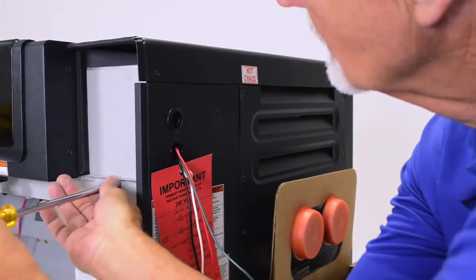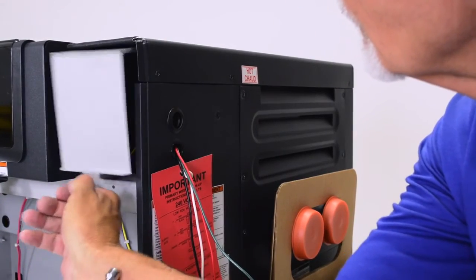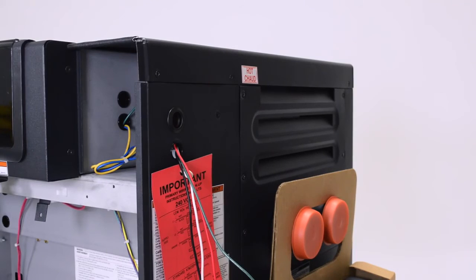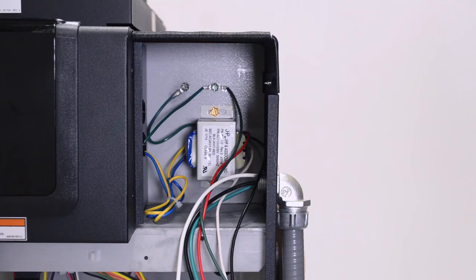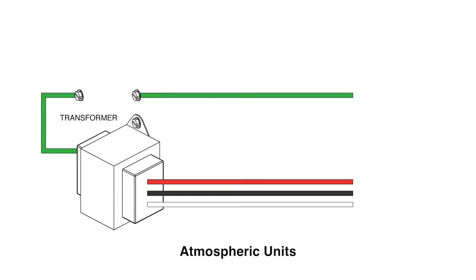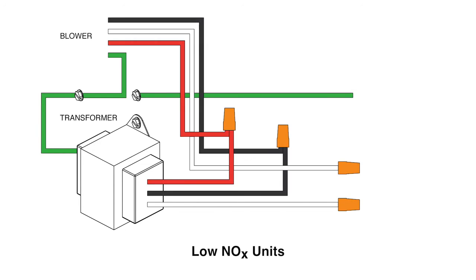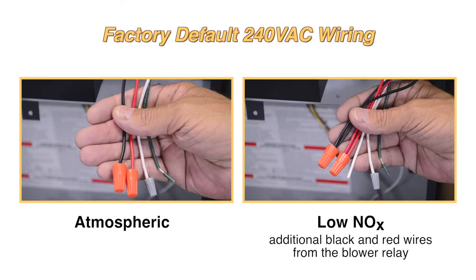Using a 5/16 inch nut driver, remove the transformer cover located on the right side of the heater. The transformer is attached to the back wall of the junction box. You will find 4 wires coming from the right side of the transformer: black, white, red, and green. On Low NOx models, you will also find these same colored wires coming into the box from the left. These lead to the relay which powers the blower.